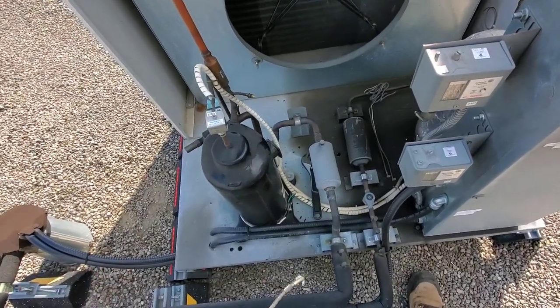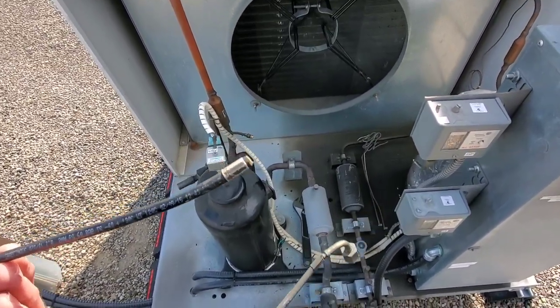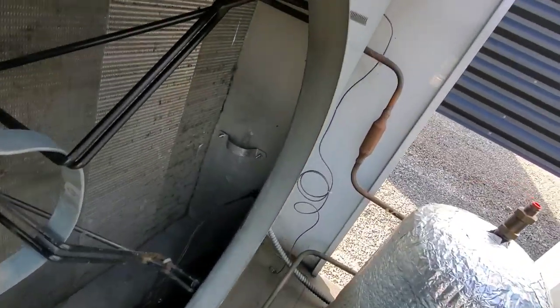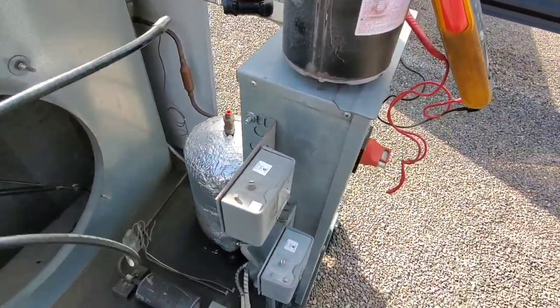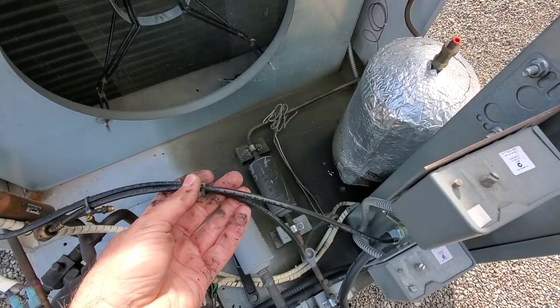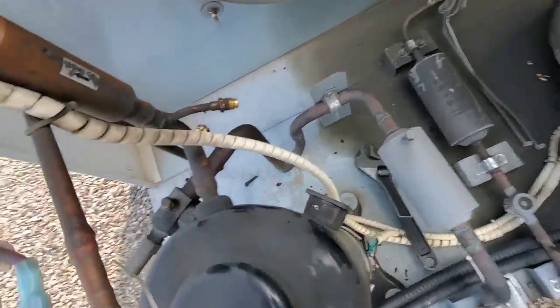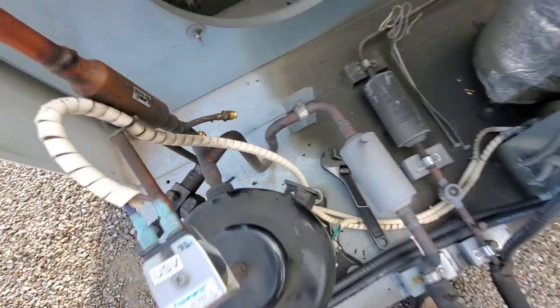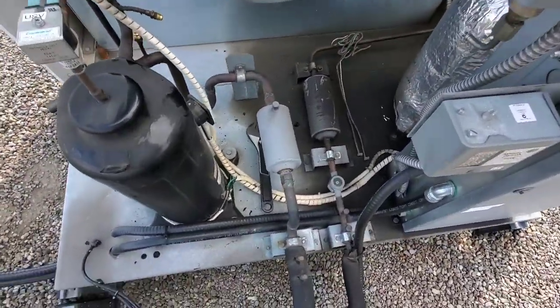So in a lot of these YouTube videos, you don't see stuff happening that's not supposed to happen. I was leaning in here — the cap was mounted back there, such a silly place. The flexible hoses were mounted, and I leaned in a little too hard and one broke right off. Luckily there were cores in both of these, I just pulled them off, and we didn't have a lot of gas leave — just a little bit of vapor.